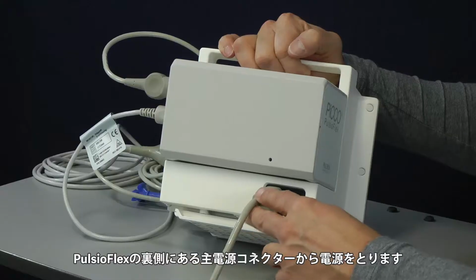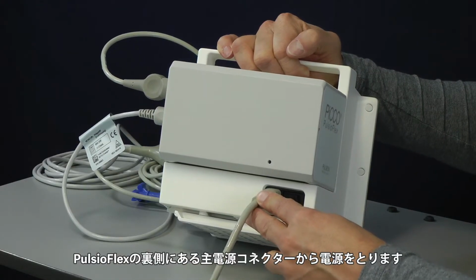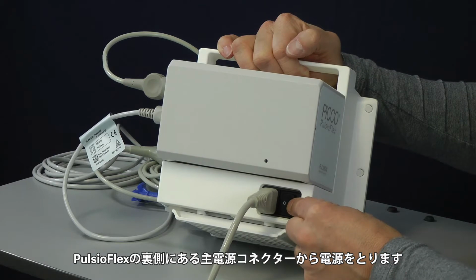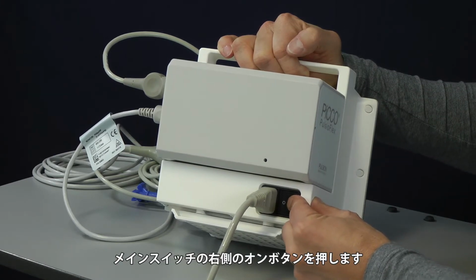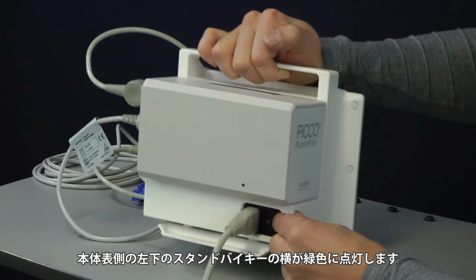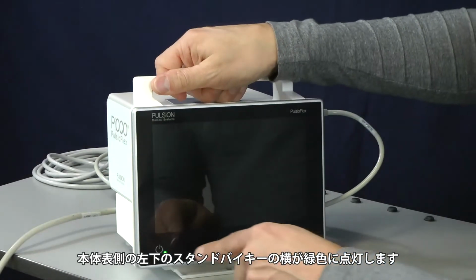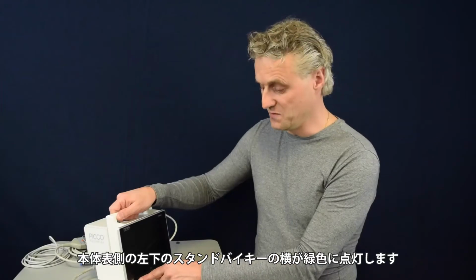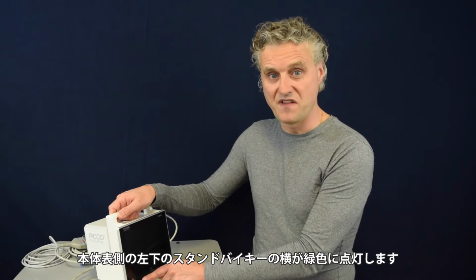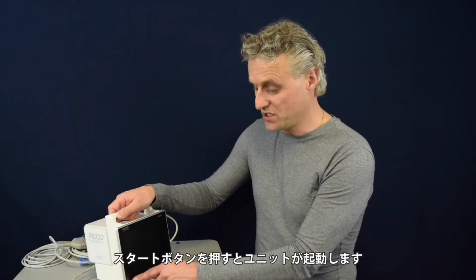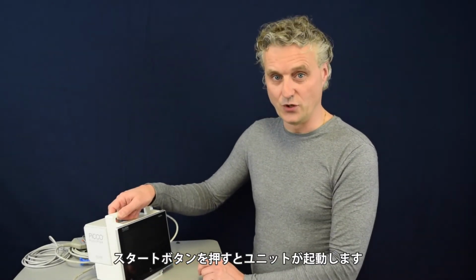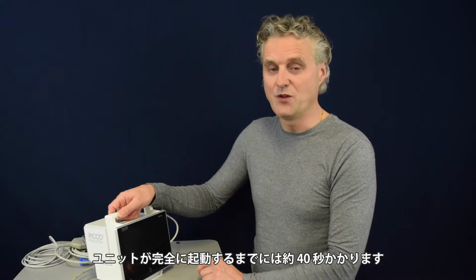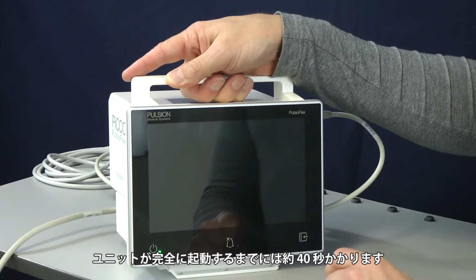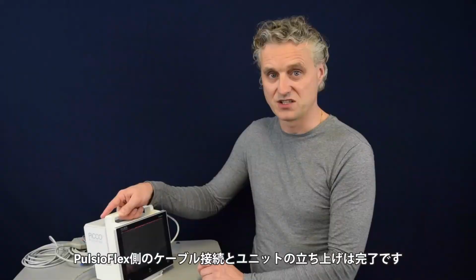After entering the power cord at the back side of the PulsioFlex, you just need to switch on the device by just pressing the button. When you turn on the unit, you will see that there will be a green light. This means there is power on the device. When you touch the on/off button, the unit will start up. It will probably take about 40 seconds before the unit is completely started up.